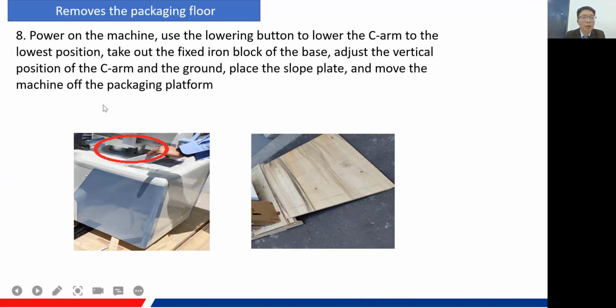So let's power on the machine and use the lowering button to lower the C-arm to the lowest position. And take out the fixed iron block of the base. Adjust the vertical position of the C-arm and the ground. Place the slope plate and move the machine off the packing platform. And this wooden piece is for moving down.